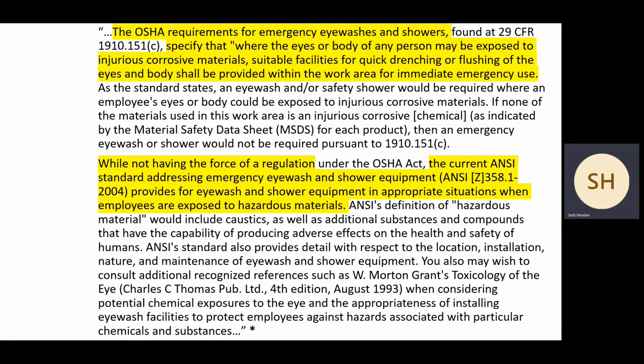That is the rule. And the door has to swing open, by the way. So you can't have to pull it, you have to push it. So if you're standing in your assembly area and you think that it would take more than 10 seconds, which is usually about 10 big steps, and you have to go through more than one door, and that door isn't a push, then you would say, okay, I'm actually not compliant with this OSHA regulation, and it looks like maybe that eye wash station has to come back, or I need to ask for one to be installed.